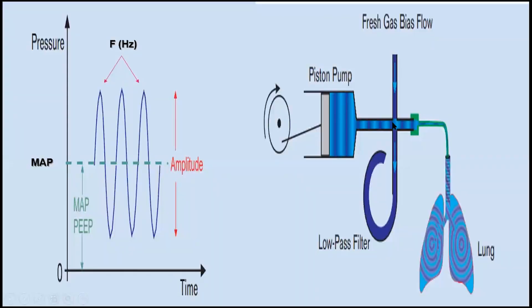Simplified, the HFOV machine uses a very high bias flow entering the machine, controlled by inspiratory and expiratory valves. This flow creates a constant distending pressure delivered to the patient's lungs. The flow is connected to another chamber containing an oscillator — usually a piston, or sometimes a diaphragm or membrane. This oscillator moves very rapidly in and out of the airway, pushing air in and pulling air out, creating rapid pressure changes or oscillation around the mean airway pressure.